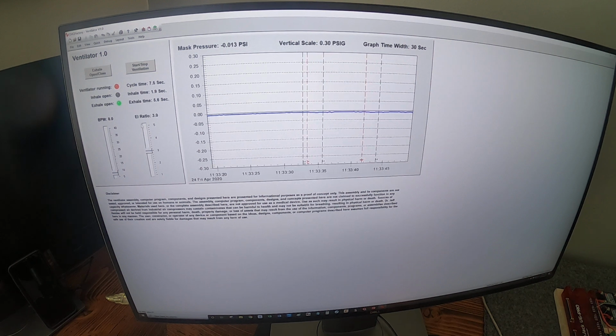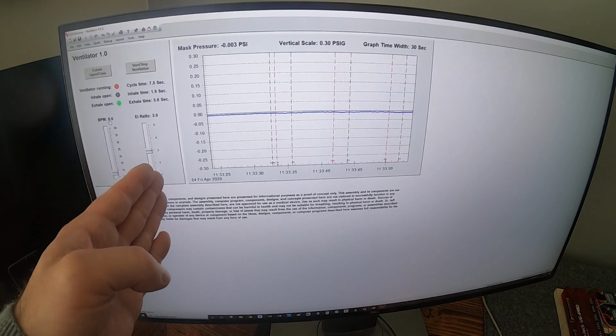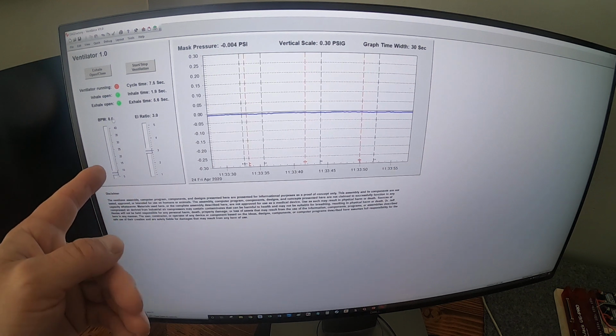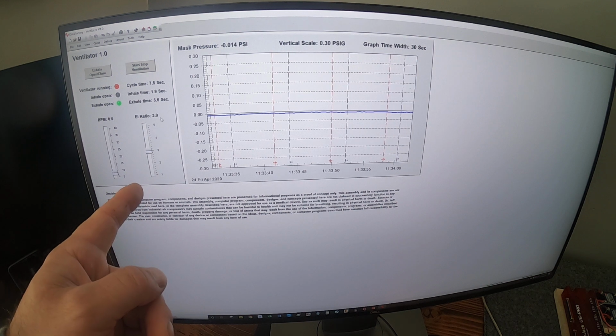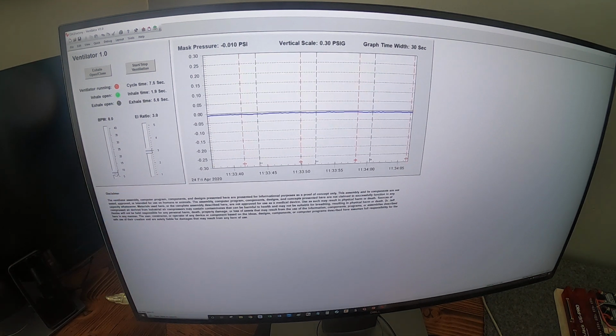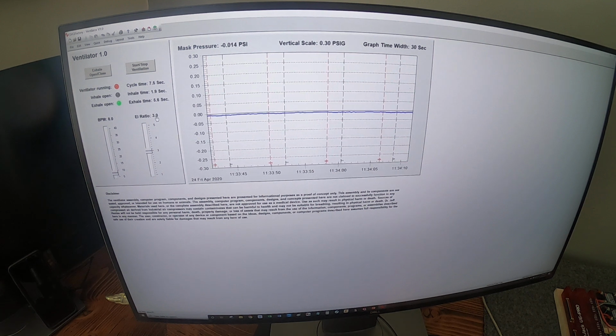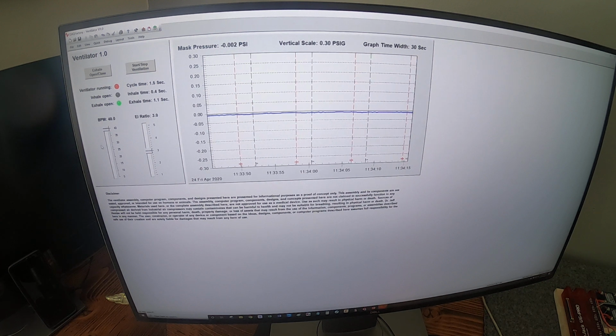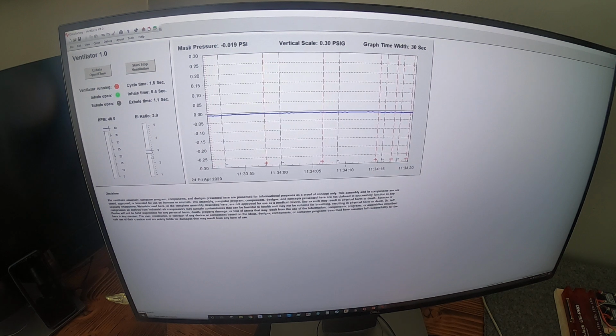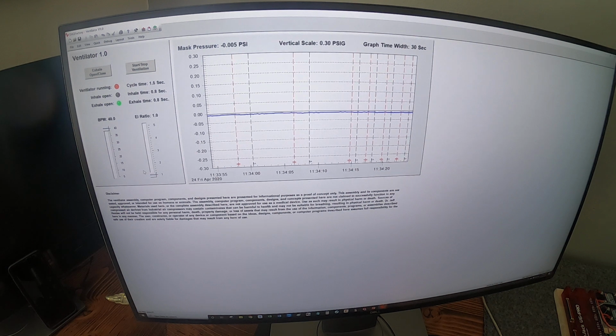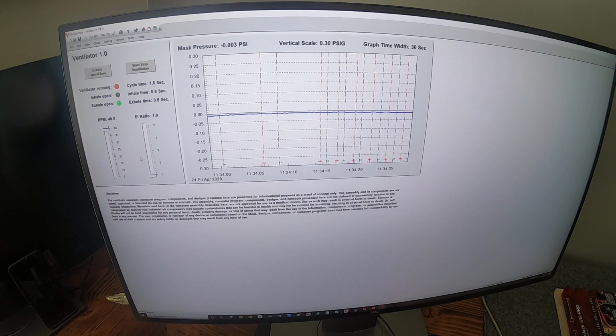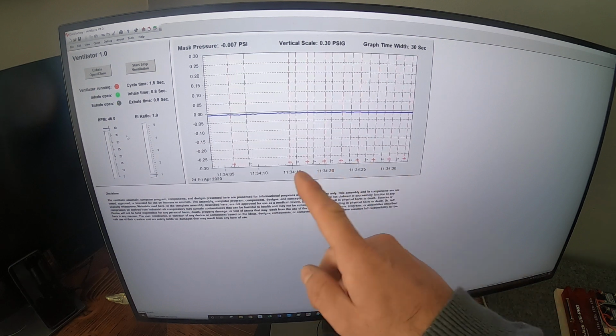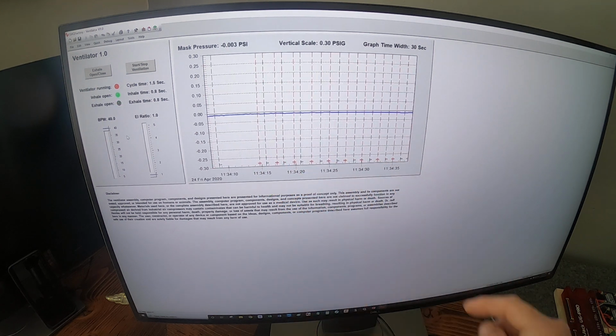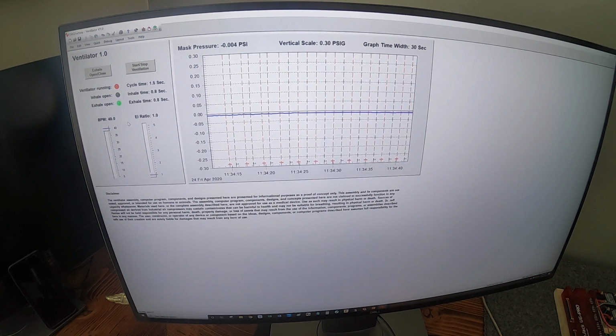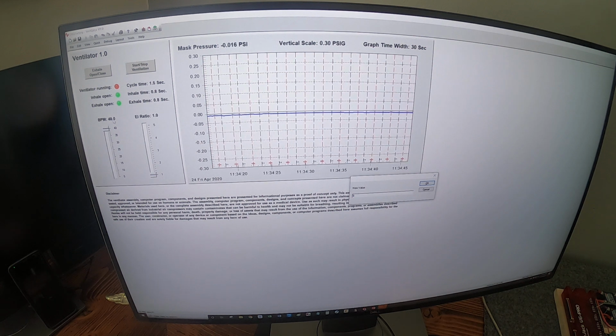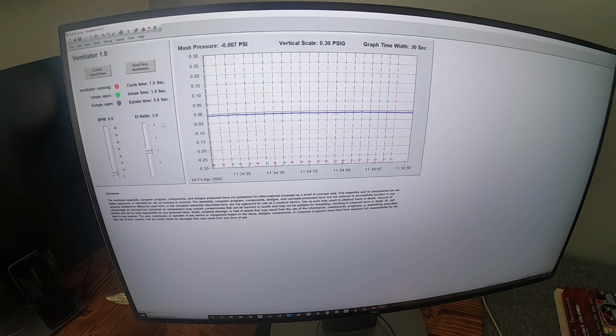The 2 controls that control the automated ventilation cycle are the breaths per minute and the exhalation to inhalation time ratio. I found with this unit, at least testing on myself, that 8 breaths per minute and an exhalation-inhalation ratio of 3 are appropriate. These values can be edited with the sliders or by clicking on the respective value and typing it in. I'll turn it up to a fast rate of breaths per minute so you can see that it cycles faster. Similarly, we could turn the exhalation-inhalation ratio to 1. In this case, it's using an equal amount of time for the inhalation and exhalation. And you can see the strip chart here gets marked with red and black lines showing when the inhalation and exhalation valves are open. We'll use this direct data entry function to set these parameters back to more realistic settings.